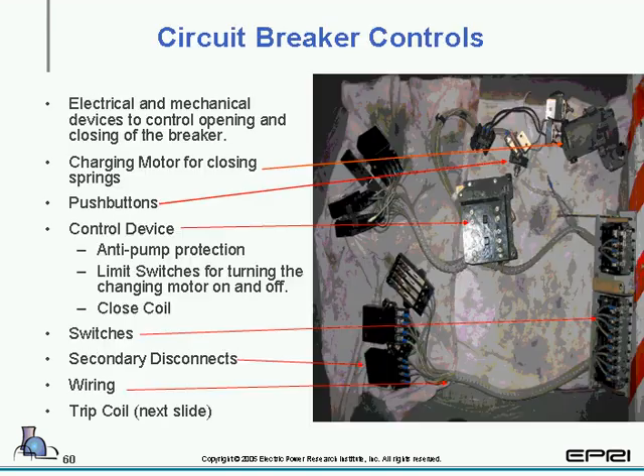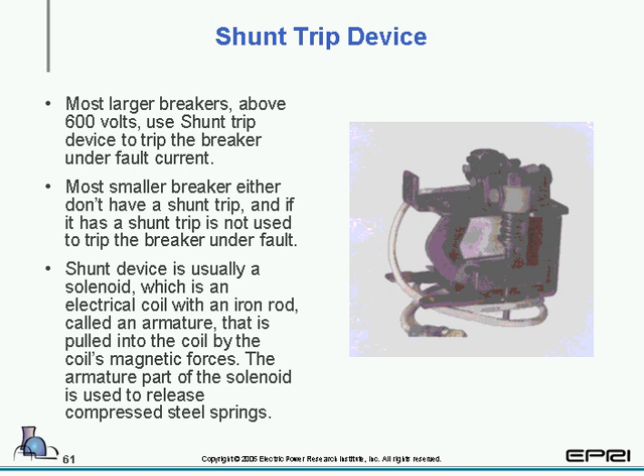Take a look at circuit breaker controls. Electrical and mechanical devices to control the opening and the closing of the circuit breaker. Most, if they're electrically operated, will have a charging motor, push button, control device, which may have the anti-pump, limit switches, and close coil. You have auxiliary switches. You have secondary disconnects, wiring. And we'll be taking a look at the trip coil on the next page.